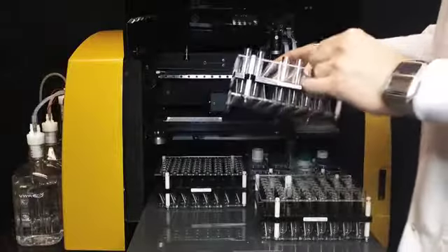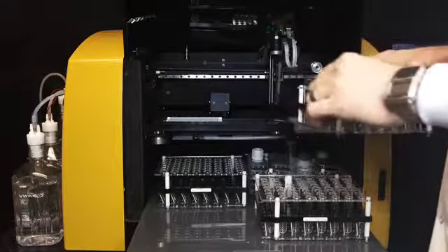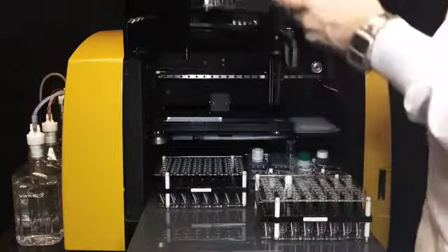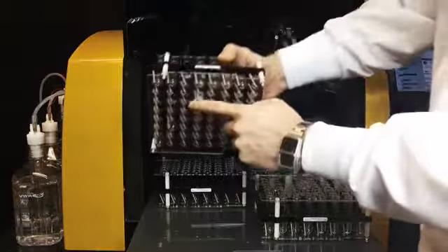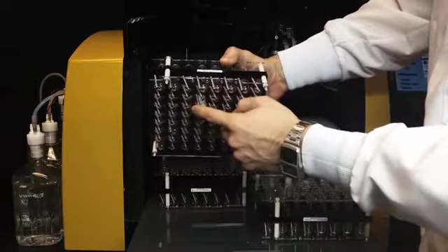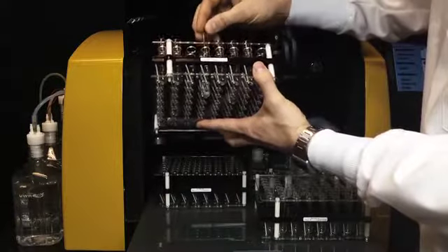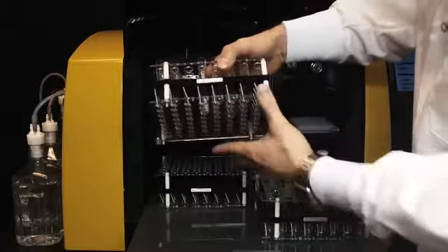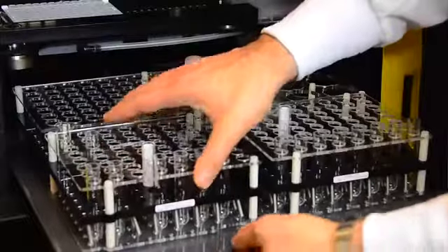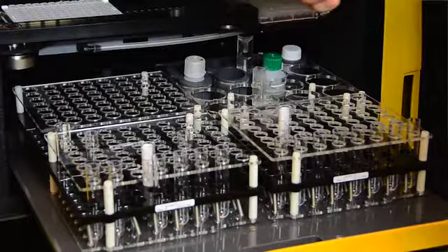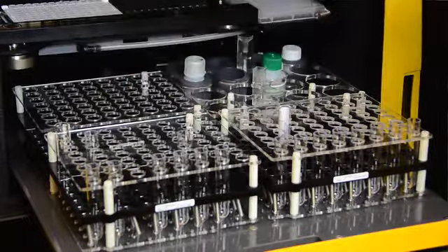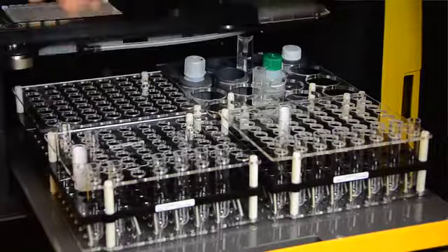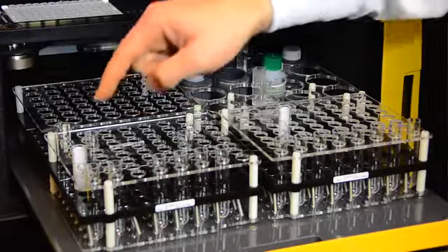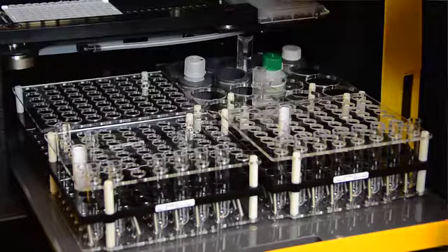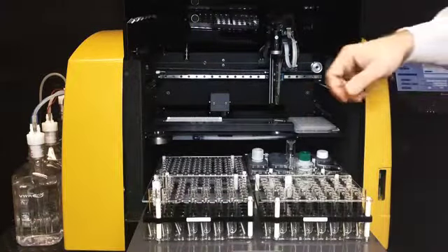I just wanted to talk a little bit more about the intelligent racks. Now, the way that we detect the location of the sample tube is by magnets on the bottom of these springs. So when a sample tube is placed in here, the spring moves, meaning the magnet moves. Below this deck are detectors that are here, here, and here. So any movement of a magnet above them will be detected. That's how, if we scan in this barcode and then place it here, that magnet will move, and the detector will know that that sample was placed there. That is our positive identification system, and that is how it is done.